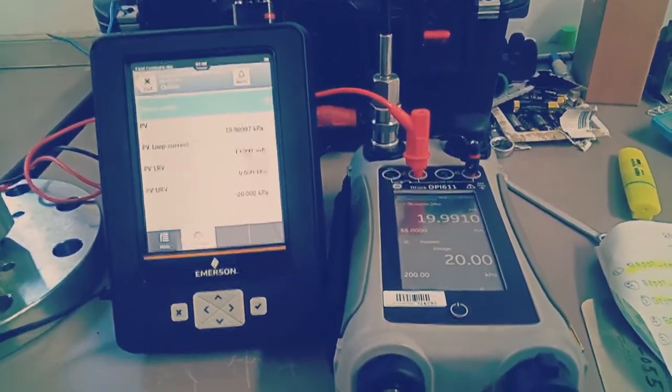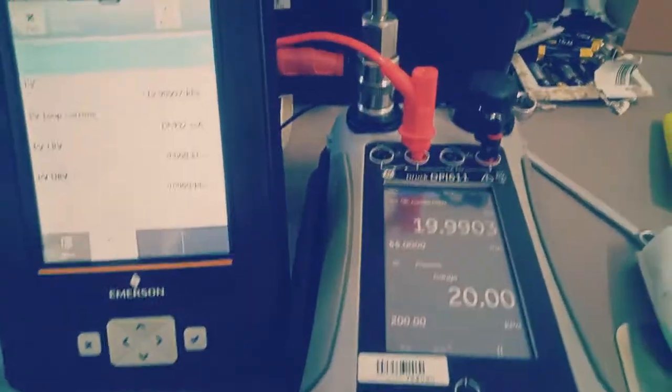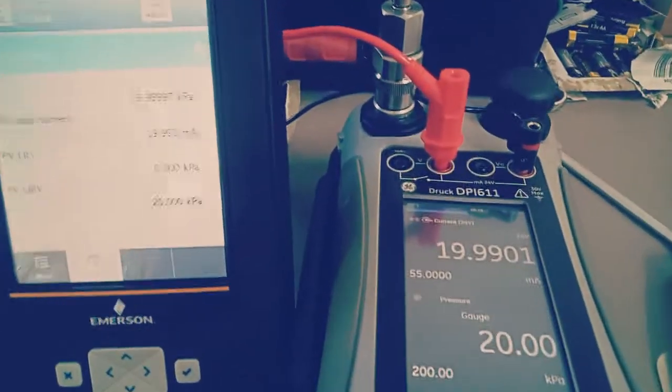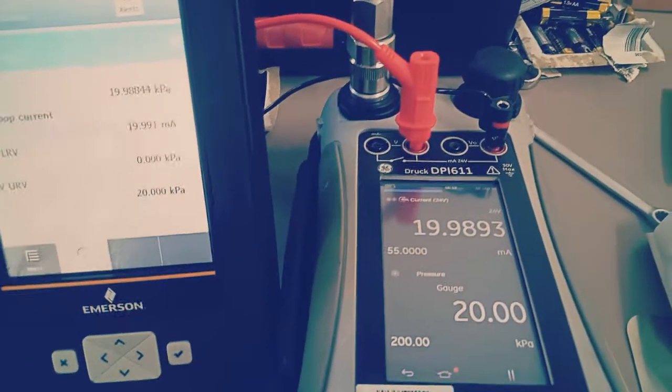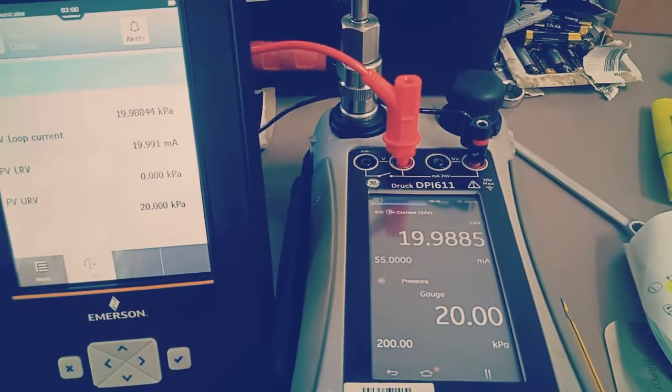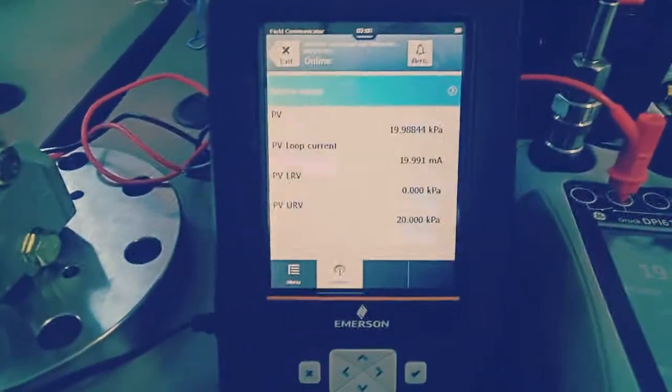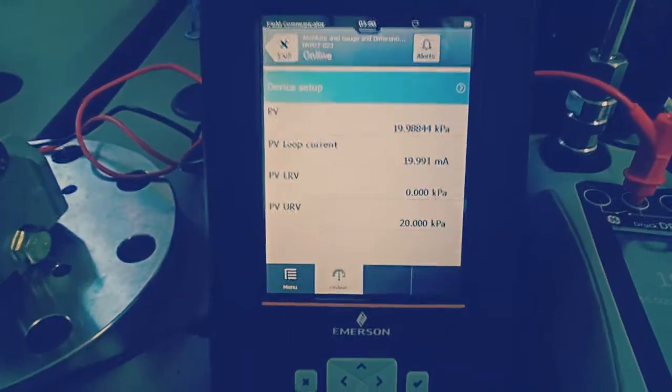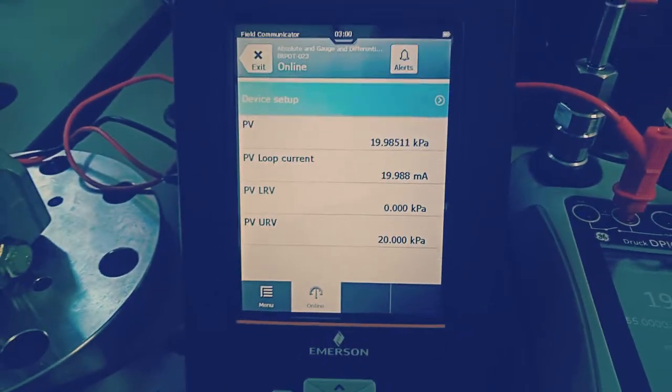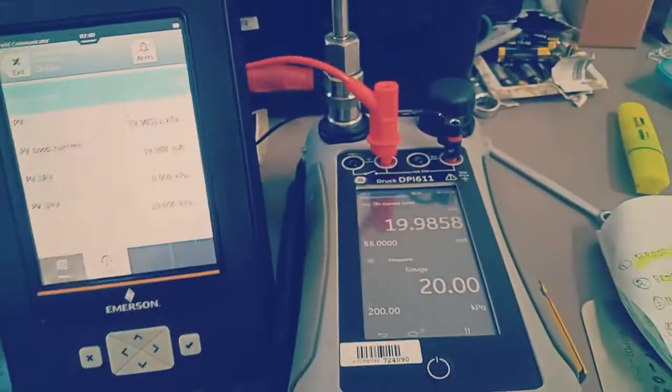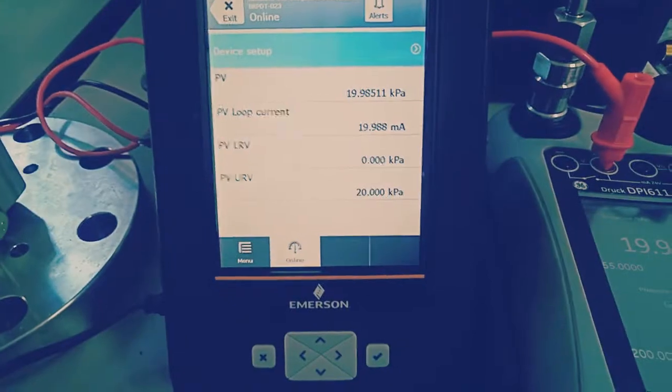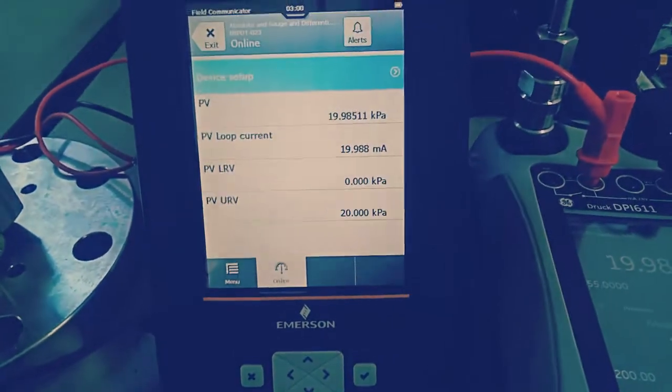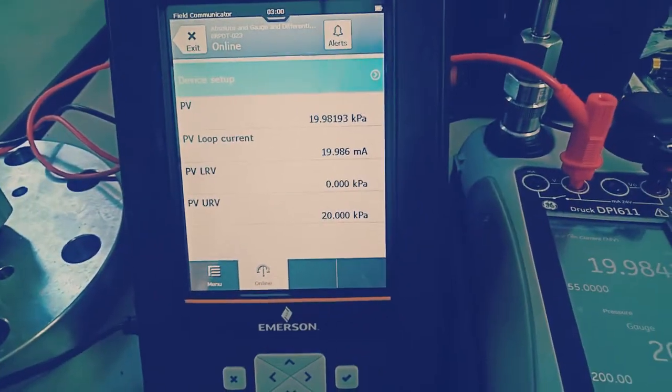Okay, this is our 20 kilopascal, and what we get is 19.989. The HART value, due to the drop of pressure there is a little variation, but it is still acceptable and under the tolerance limit.